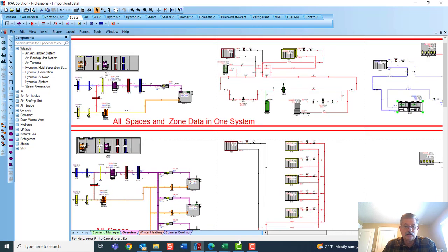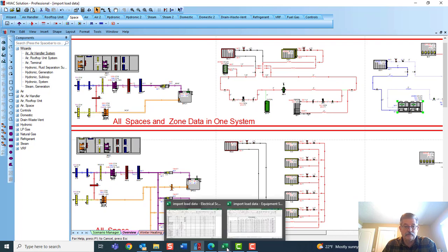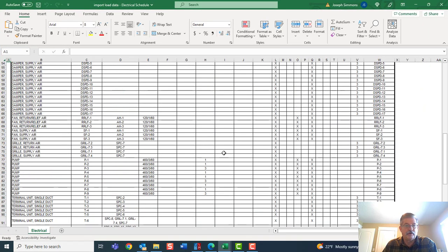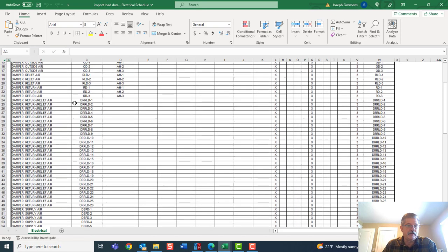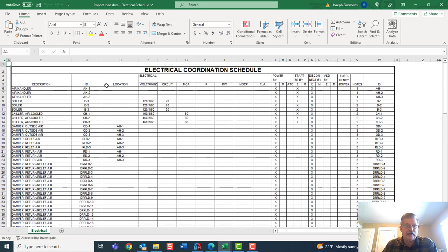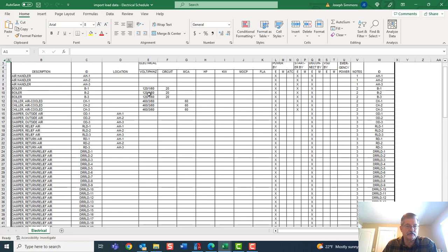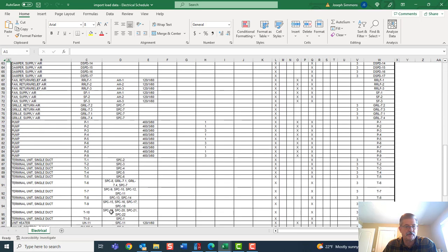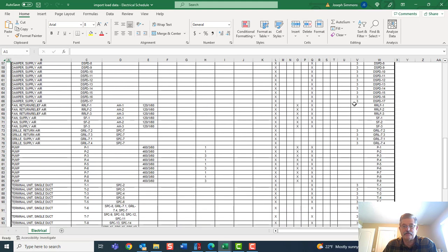As well, I also know all that load data down here, electrical information, and anything that needs power, dampers, boilers, pumps, has it indicated over here. Then when it's automatically selected, it appears here. And then who's providing the power, the starters, mechanical, electrical disconnects, are there VFD drives, emergency power, and then notes that are all associated that you can put at the bottom to clarify other things.